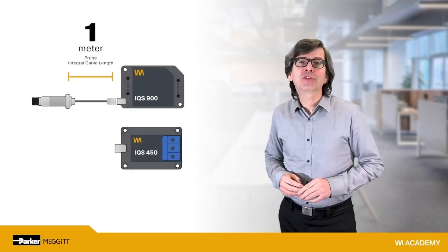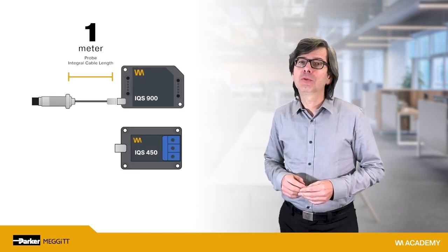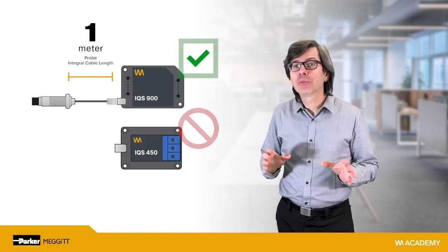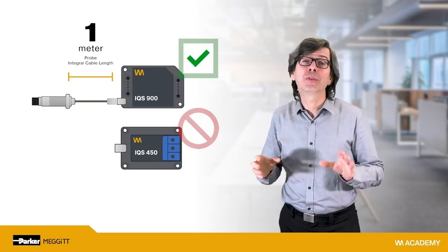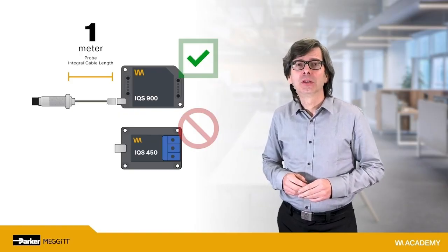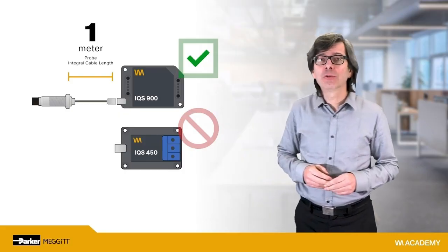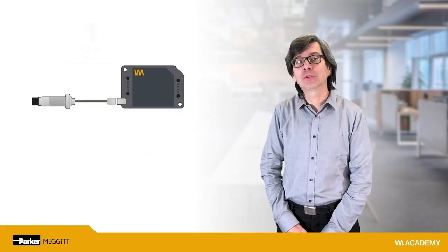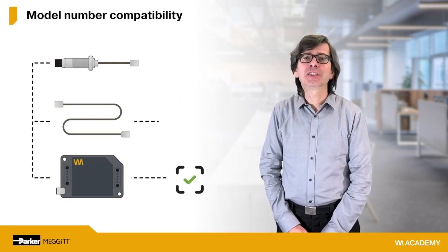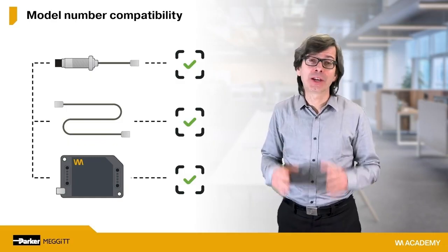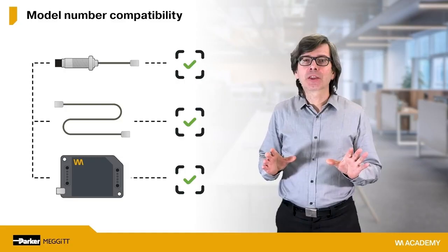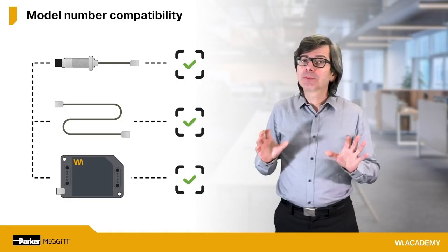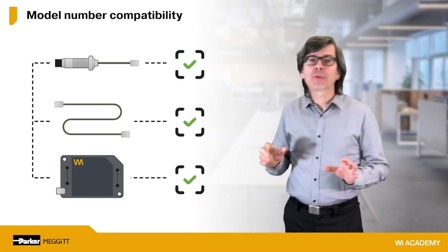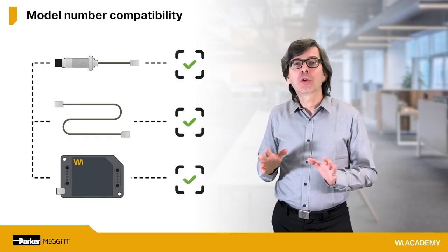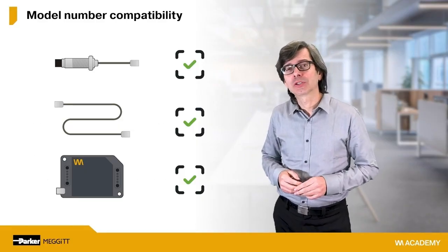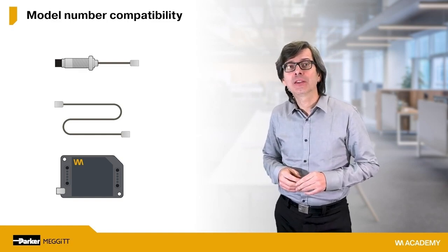It is also worth pointing out that the 1 meter tuning length is only available in the newer IQS 900 signal conditioner, which can be used with both 400 series and 900 series of 8mm or 5mm probes. The 1 meter tuning length is not available in the older IQS 450 signal conditioner, and instead only in the newer IQS 900. Later in this lesson, we will discuss the compatibility of probe, cable, and signal conditioner model numbers. So both total system length consideration and model number compatibility must be maintained through the system. Not all 4-meter extension cables, for example, will work with all 1-meter probes and 5-meter signal conditioners. A compatibility table is provided later in this lesson to help you in this regard.